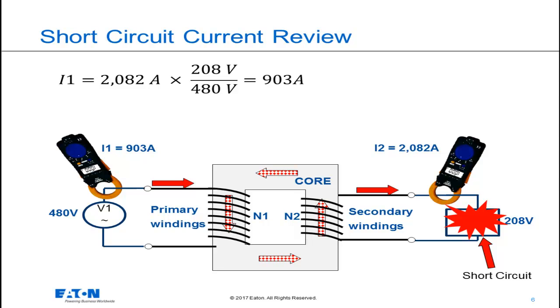From a selective coordination perspective during a fault, the overcurrent protective device on the secondary would see 2082 amps flowing through it. The overcurrent protective device on the primary would only see 903 amps during this same short circuit event.